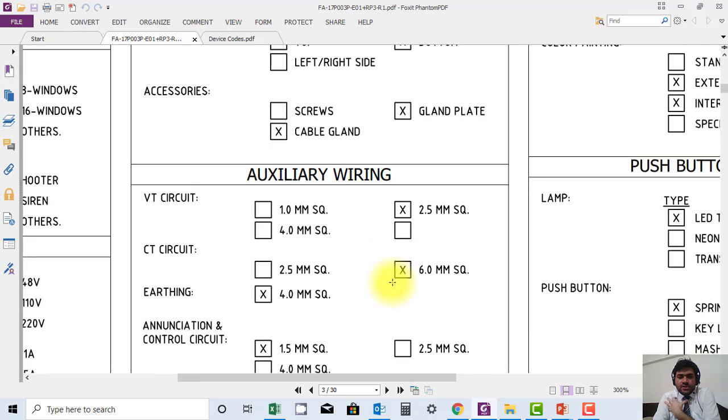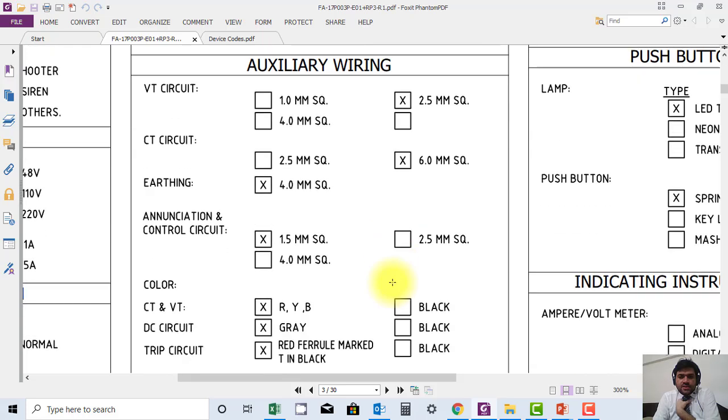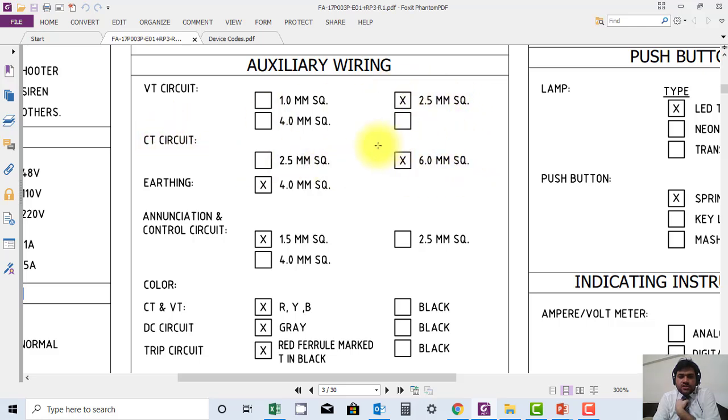Another thing, for example, they are saying that VT wires are of 2.5 square mm and CTs of 6 square mm. You can see our thing is done through 4 square mm, so this is very useful information.